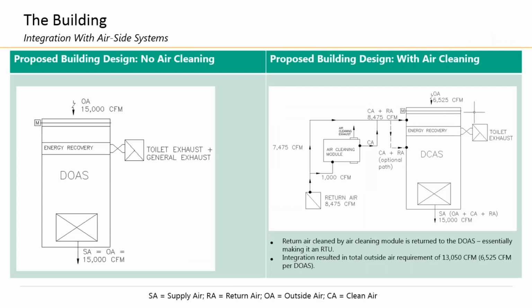Let's talk about a quick application here. Now, I know many folks here are not mechanical engineers. Many folks might be in other fields, but I just want to talk really quickly. We get frequently asked how you would apply this to a 100% outside air system. So 100% outside air DOAS system here, the proposed case on the left, where you're drawing in 15,000 CFM of outside air. We've got energy recovery treating toilet exhaust and general exhaust. And then there's 15,000 CFM of supply air. Pretty standard building, okay? So you say, Ted, I don't have a return because I've got a DOAS system.